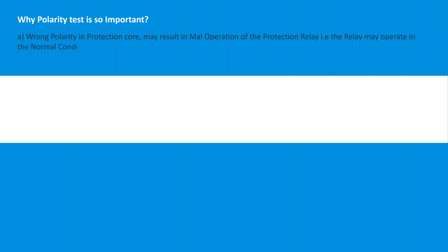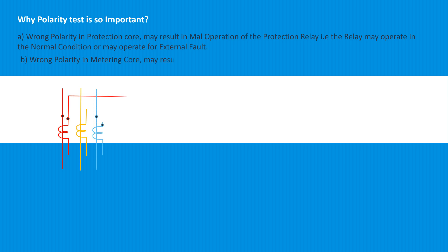Why is the polarity test important? Wrong polarity in a protection core may result in mal-operation of the protection relay — that is, the relay may operate in normal condition or may operate for an external fault. Wrong polarity in the metering core results in wrong metering.